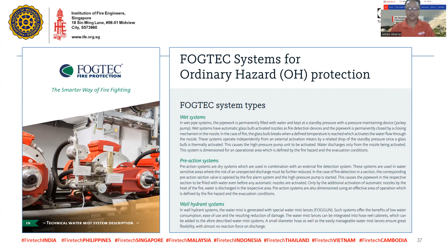Wall hydrant system: the water mist is generated with special water mist lances. Such systems offer the benefits of low water consumption, ease of use, and the resulting reduction of damage. The water mist lances can be integrated into hose reel cabinets, which can be added to the aforedescribed water mist system. A small diameter hose, as well as the easily manageable water mist lances, ensure great flexibility with almost no reaction force on discharge. So there is a smaller hose diameter because it's high pressure on the hydrant system.